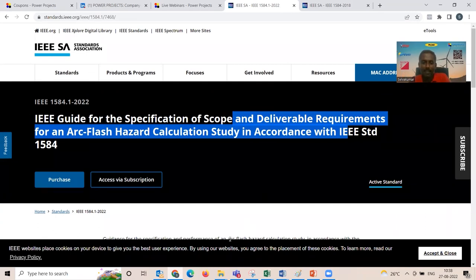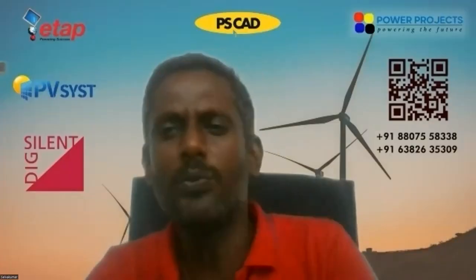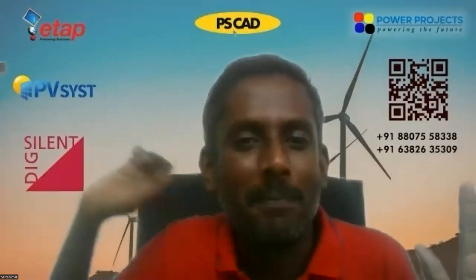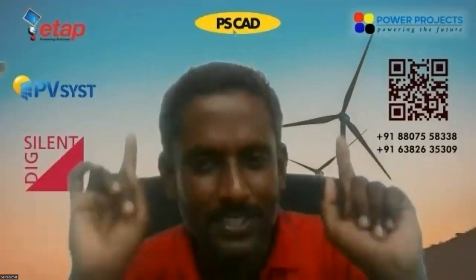Having said that, let's come back and ask a quick question. Why do we need an arc flash study? Why do we need to perform an arc flash study? By performing an arc flash study in ETAP or some other simulation software, personal safety is not ensured. That's the first point we have to understand. If you want to ensure the protection of persons, if you genuinely care about the people, buy arc-rated switchgear, don't do live maintenance, and no arc flash study is required, your people are safe.